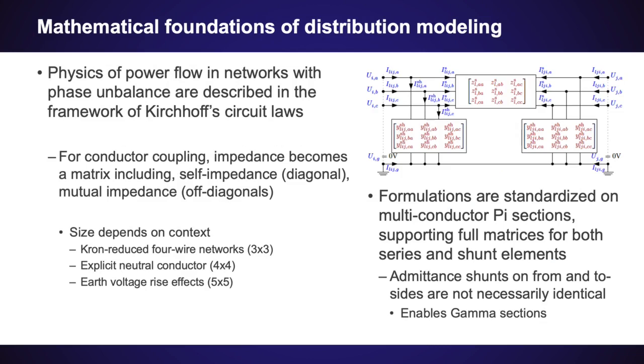What these challenges mean in practice is that the components must be modeled as explicitly multi-phase. For example, in the case of branches, the physics of power flow under phase imbalance are described in the framework of Kirchhoff's circuit laws, and therefore the coupling of neighboring conductors requires the impedance to be a matrix that includes both self and mutual impedance, where the size of that matrix depends on context — you could have a three-by-three or even up to a five-by-five matrix.